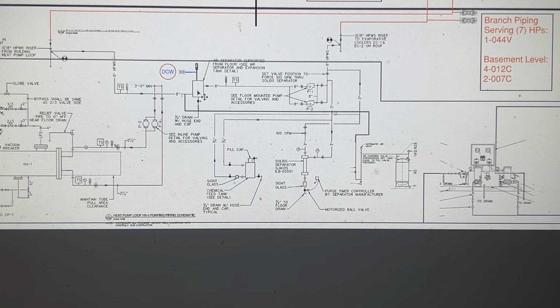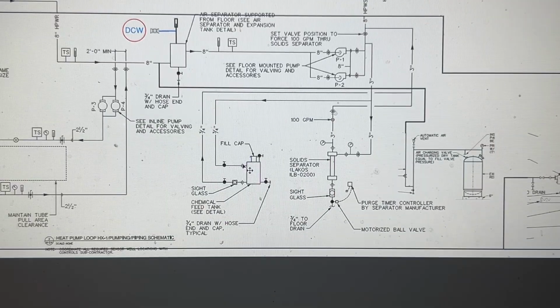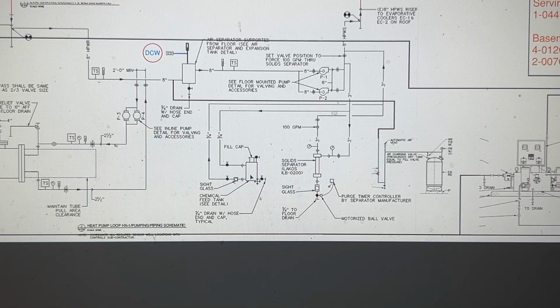So we have an air separator with a domestic water makeup in the event that water pressure dropped to some extent. This domestic water would add water to that system. There's also a chemical feed tank here, which we will treat the water as required. This allows us to put chemical into this tank, and the flow of the system will push that chemical into the system to treat it.